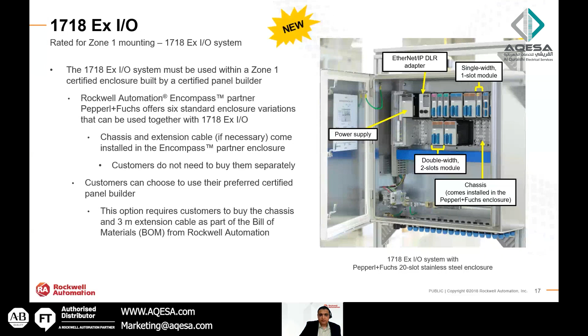So what are the benefits of 1719 and 1718? They allow IOs to be mounted closer to field devices. You don't lay multiple cables. Ease of configuration by Logix 5000. It is Ethernet port, dual Ethernet port. Scalability: you can have 8, 12 or 24 slots. Here you can have 10, 20, 30 or 40 slots. HART 7 is supported. HART 7 means you can get all the HART information you need. Power supplies can be multiple redundant power supplies.